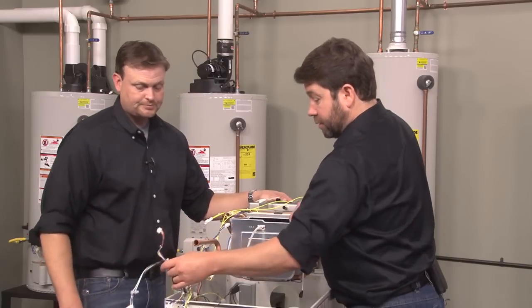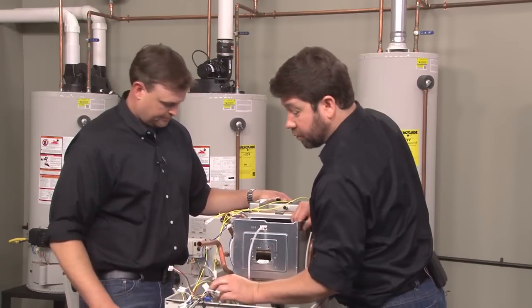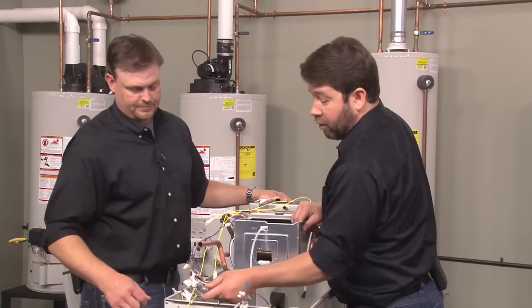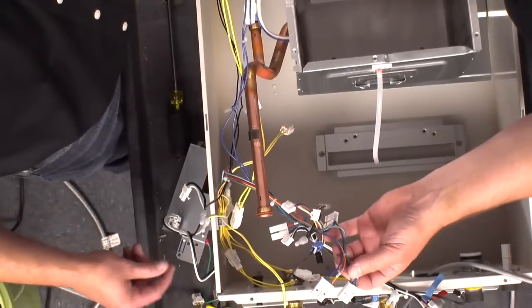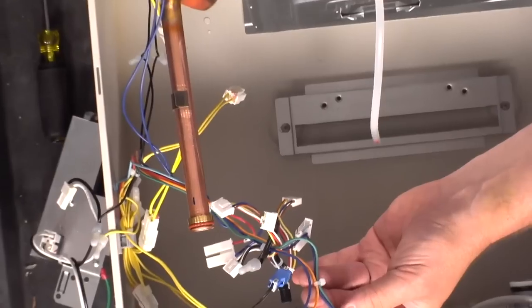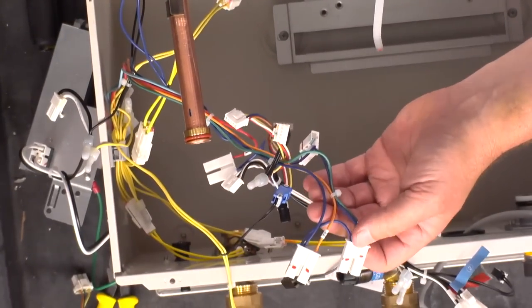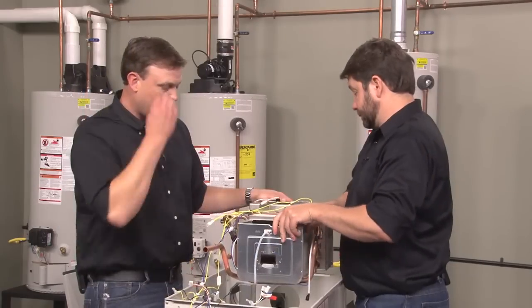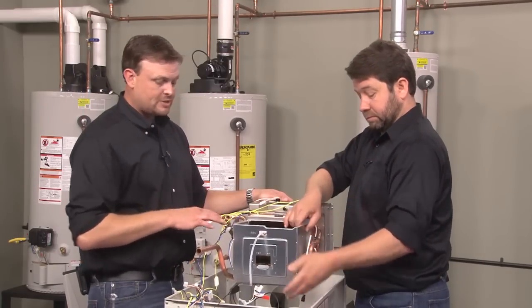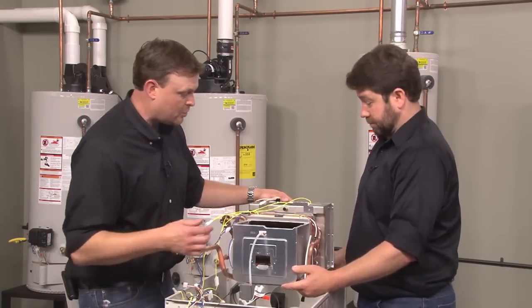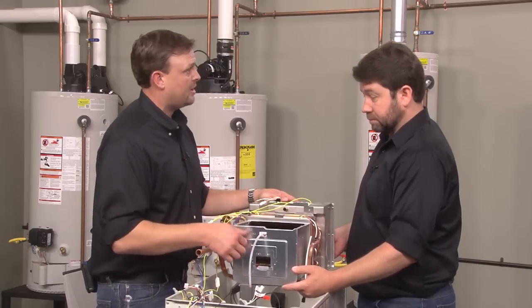If we go back to our gas valve harness, all of the harnesses have that blue wire in common. So when we leave the gas valve, after we send power to it, we go out to that blue wire, then run through our safeties. If one of those opens up, it kills power to the gas valve, and we won't be able to make fire.